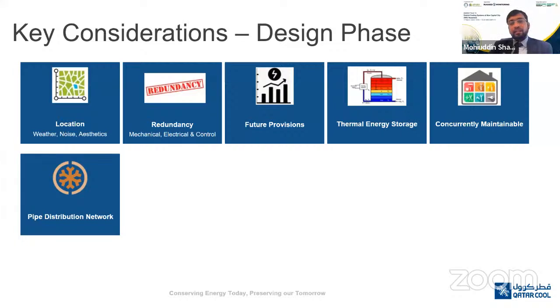Piping and distribution network and valve chambers. So the PDN has to be designed taking into consideration, especially if you are in the coastal area, the water table. I am assuming the water table would be high, as Qatar is an island nation, same as Indonesia. So the water table is high in the areas where we serve. So that poses a challenge to us, having a properly designed piping system to take care of corrosion because of the seawater. That is critical. And the sizing of the distribution network has to take into consideration the capital cost against the operation cost, and the future expansion, corrosion, etc.